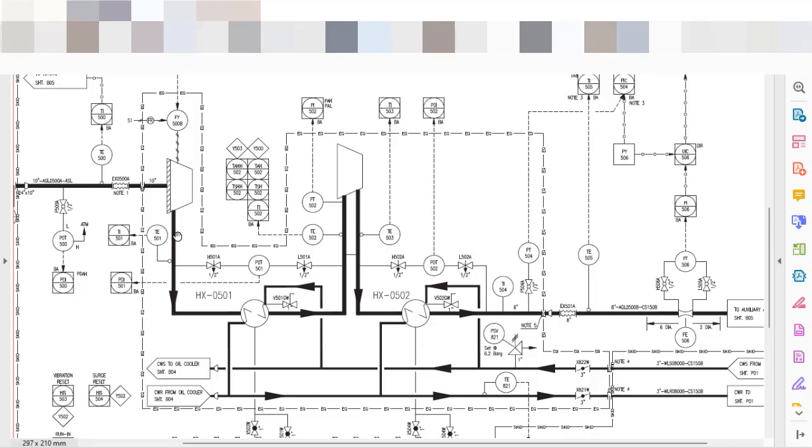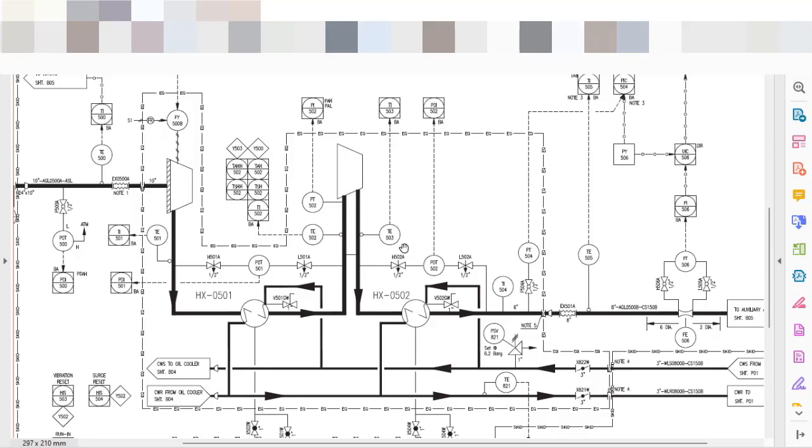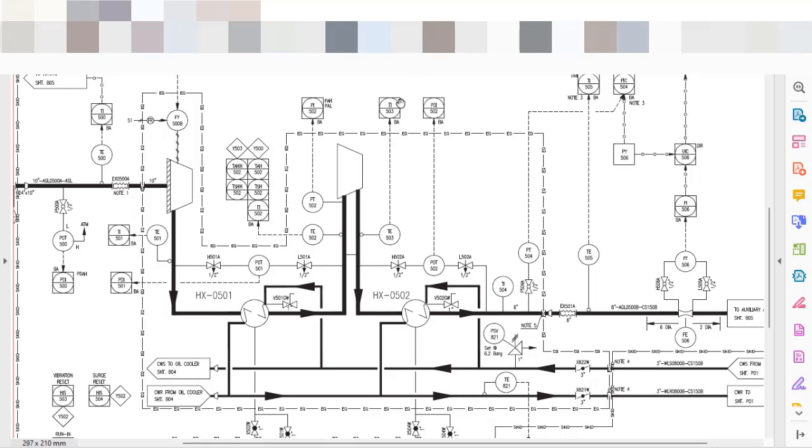And here you can see why I have dash lines going outside of the boundaries or the battery limits of the equipment. I have this because, for instance, this TE represents the temperature element for the temperature measurement and also it's like a transmitter. So the signal transmitted by this element will go to my PLC. So this square with a circle here and a dash line here represents that this information will go to my supervisory. But before going to the supervisory, I need to add the cables to connect to my PLC. So the communication between the TE and the supervisory is based on the PLC arrangement.